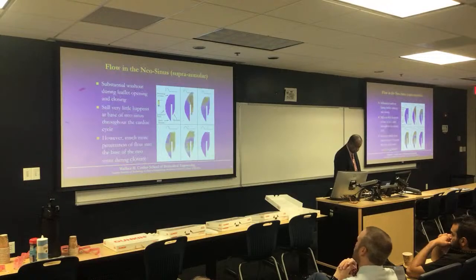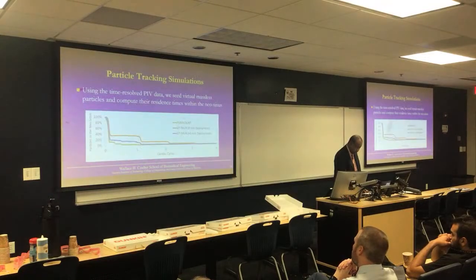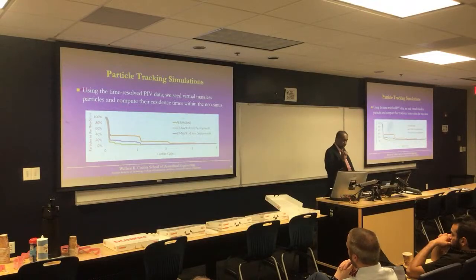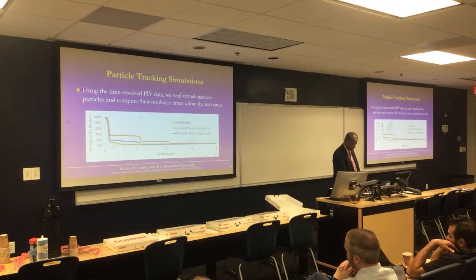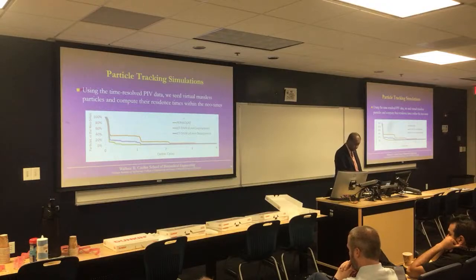And what we found was, if we looked at those measurements and then simulated washout in that pocket region, you could see the varying regions for various designs. This was what we call a 0 deployment, a 5mm deployment, and compared to a surgical valve, these mimic conditions between the Sapien valve and the CoreValve. You can see that the washout is very different. And this kind of analysis now allows us to look at how the geometry of this valve varies when it's implanted in the human anatomy.